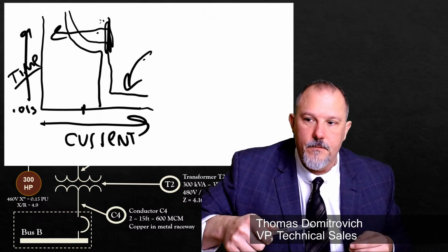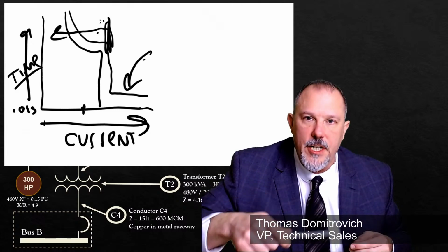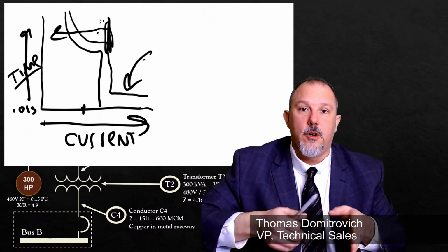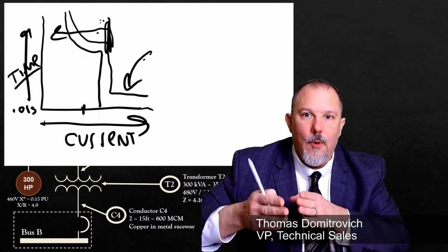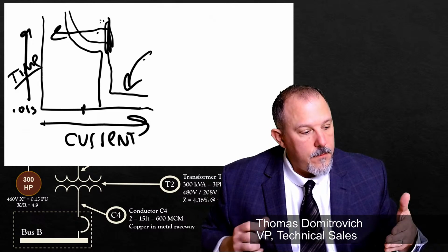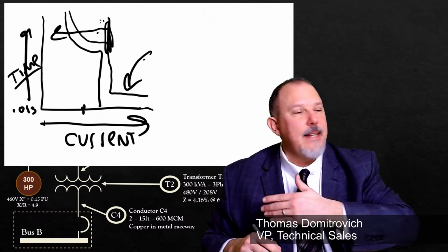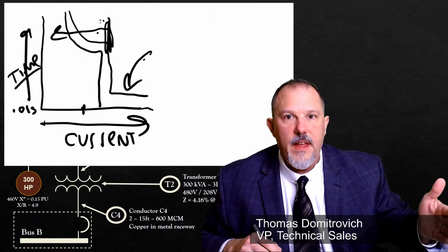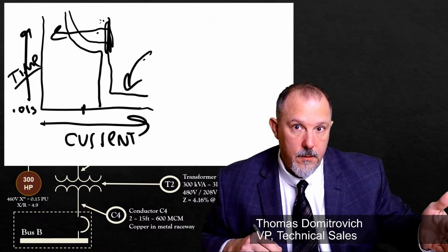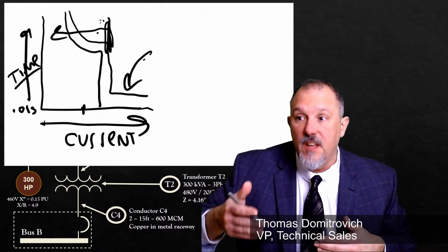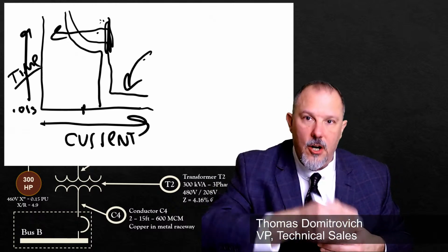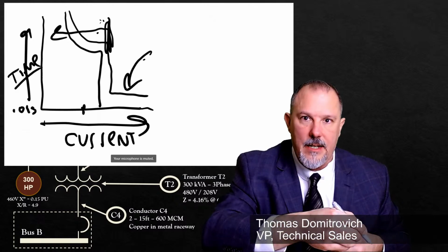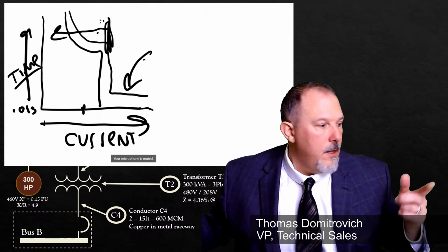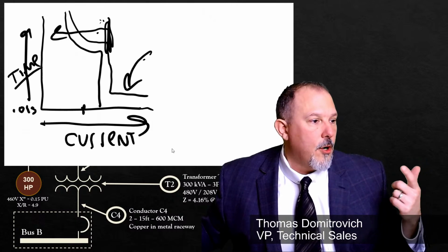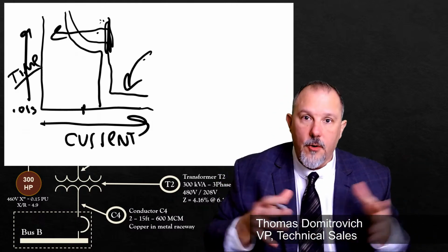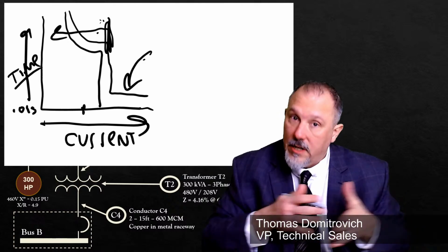Let me explain myself there. Because you're in the instantaneous region of this circuit breaker does not mean your fault current was a short circuit. And why do I say that? Because what if my instantaneous is set so low that a simple overload trips the breaker? I may have missized my overcurrent protective device. I may have put a smaller overcurrent device than I need. Just because you're in the instantaneous region does not mean, by definition, that you have a short circuit occurring in your system. It could still be an overload or a temporary overload.